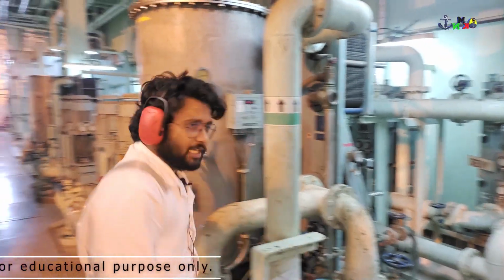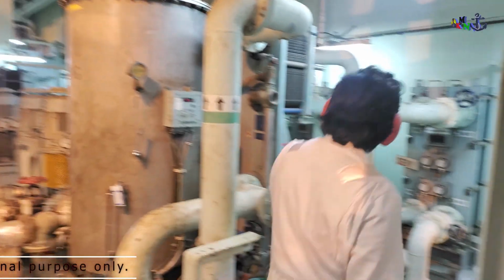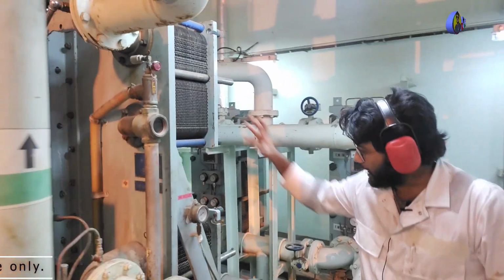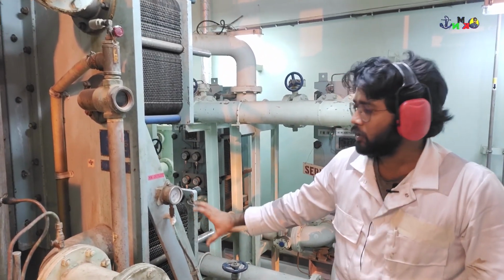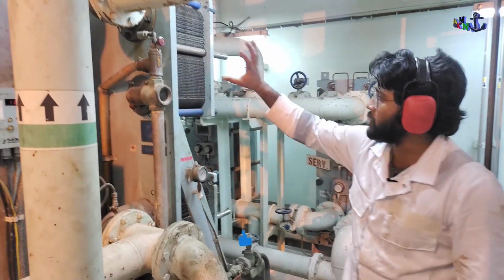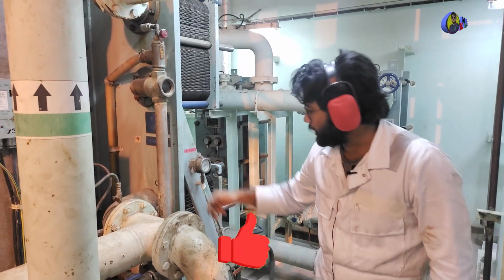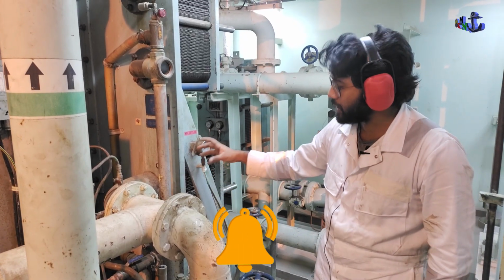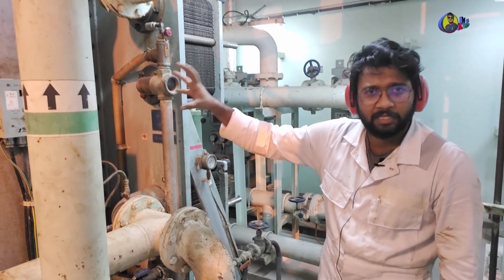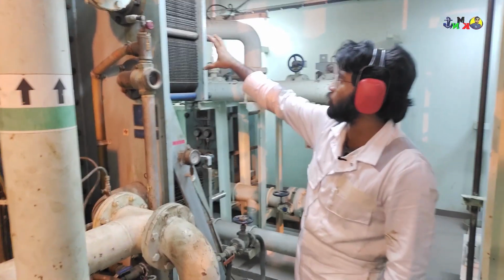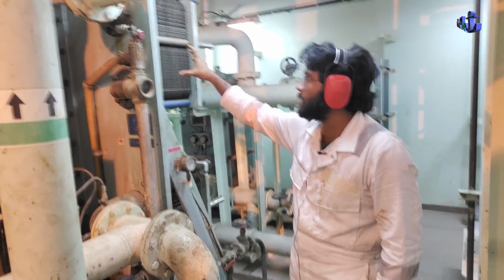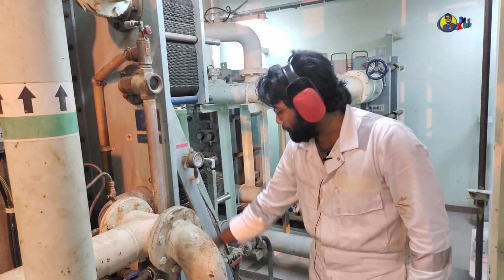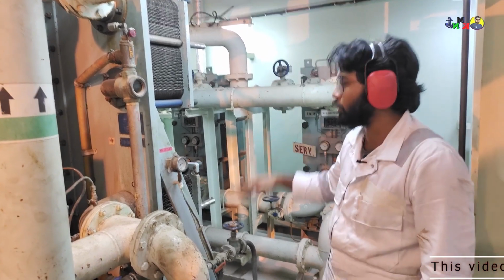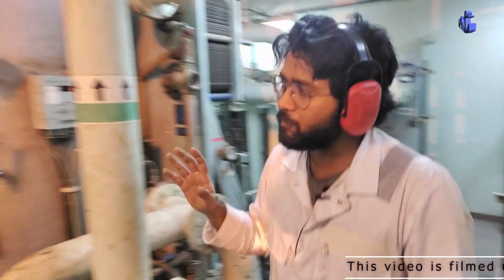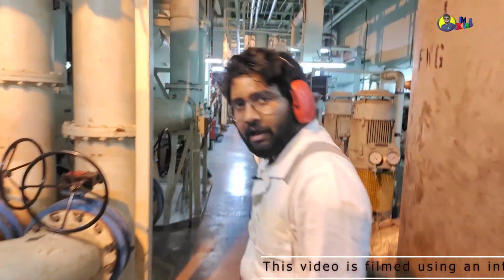So this can also generate water from seawater using steam. This is the evaporator shell, and then you have the condenser and the evaporator or heater. The seawater is coming from here, going up, and from the other side it is coming inside. This is feeding, and this is the jacket water. The water is getting heated up, going and expanding in this evaporator shell. From here the steam goes to the condenser, where it condenses and comes out from this pipe, going to the circuit or to the freshwater tanks. So this is the system we are equipped with, one here and one more on the other side.